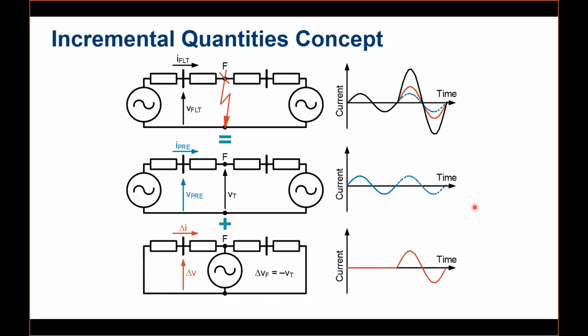Next, the concept is incremental quantities. Before, we saw the traveling wave, its advantages and some applications. Now it is time to discuss a little bit on the incremental quantities. We call them TD quantities as well, time domain quantities. The major concept, to simply understand incremental quantities, is just like a faulted circuit. What the relay will measure will always be a fault current and a fault voltage.